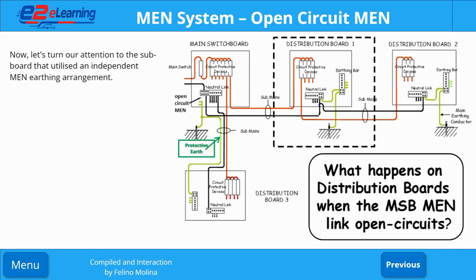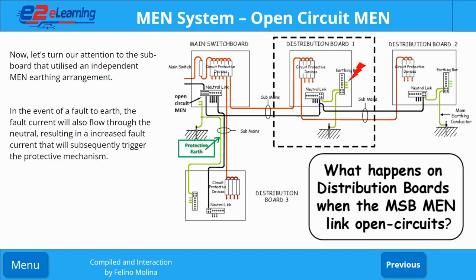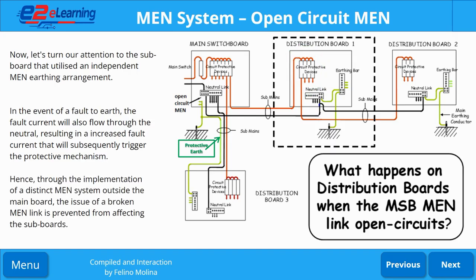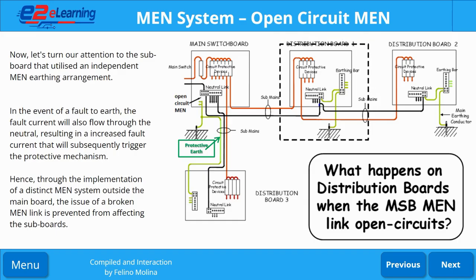Now, let's turn our attention to the subboard that utilized an independent MEN earthing arrangement. In the event of a fault to earth, the fault current will also flow through the neutral, resulting in an increased fault current that will subsequently trigger the protective mechanism. Hence, through the implementation of a distinct MEN system outside the main board, the issue of a broken MEN link is prevented from affecting the subboards.